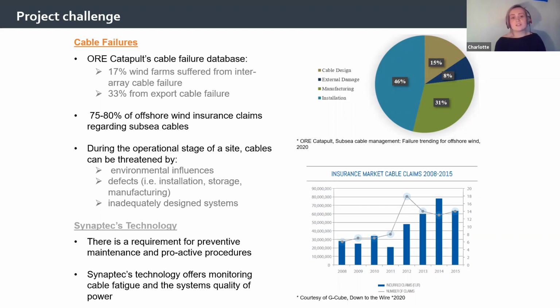Weak points are high-risk areas of the system, like joints or cable terminations. As these failures occur to inter-array cables, depending on the wind farm's fault detection methods and the redundancy a site has in place, a full string could lose generation, or the string's downtime is lengthened due to procedures for identifying which is the damaged cable.